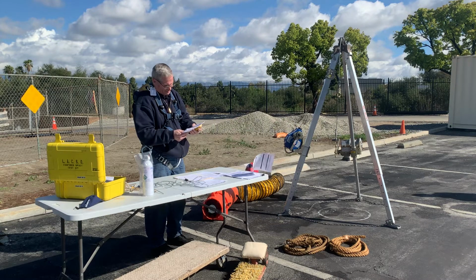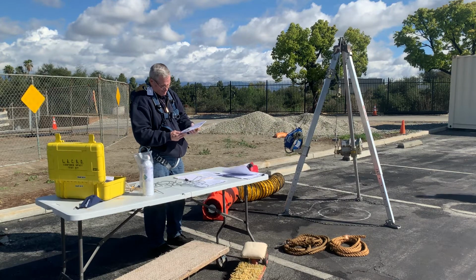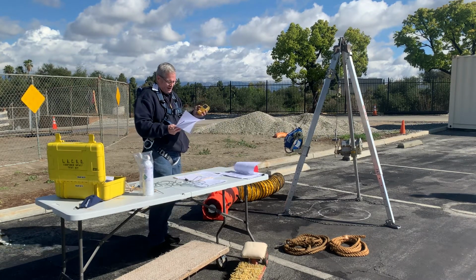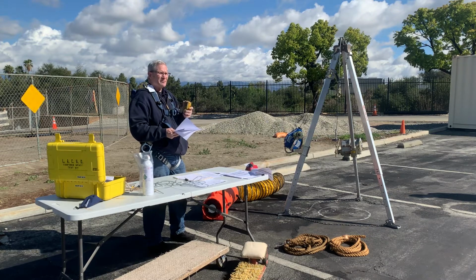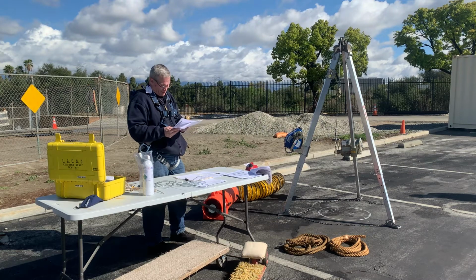A few other things. We talked about the usage of the 10-foot hose. The alarms go off, resets itself. We talked about the calibration and using the microdock too. So when would you have to recalibrate? If you drop it on the ground. If you're reading real high concentrations for whatever gas it is, you might have to get it back to the microdock station.